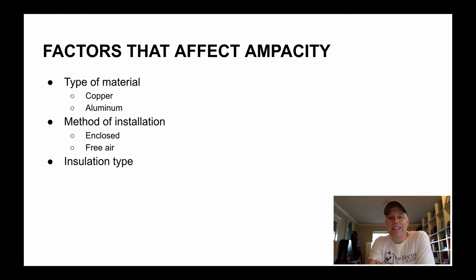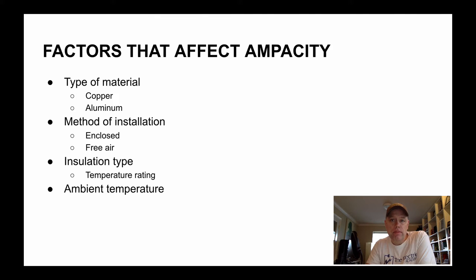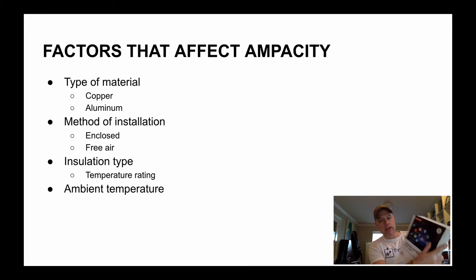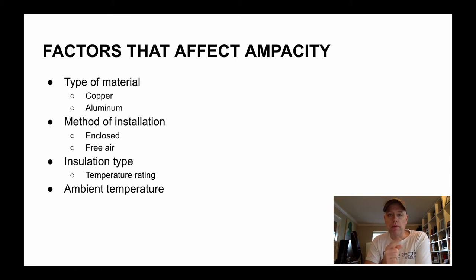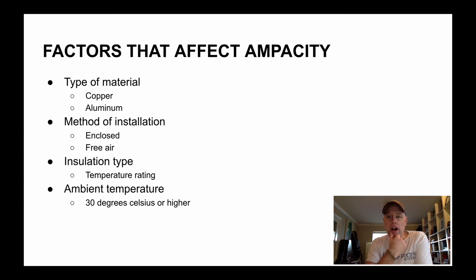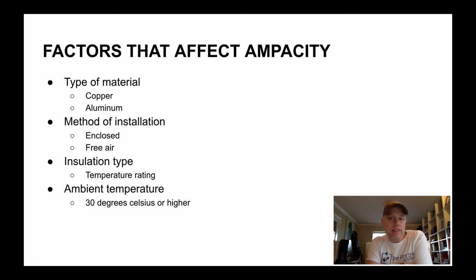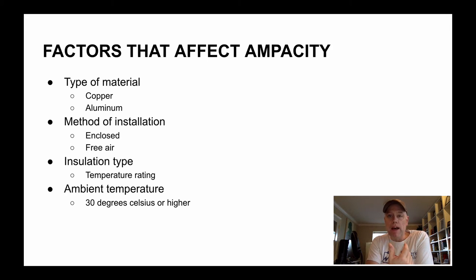Next, we have to figure out what kind of insulation we're dealing with. Insulation protects the actual conductor and prevents short circuits, so we don't want it burning off — we have to consider the temperature rating of the insulation. We also have to worry about the ambient temperature in the room. Typically, according to the Canadian Electrical Code 2018, anything below 30°C we can use our tables as-is. Anything over 30°C, we have to derate. The conductors create heat when current runs through them, and if the room is very hot, we may have to derate based on the ampacity and the temperature rating of the insulation.